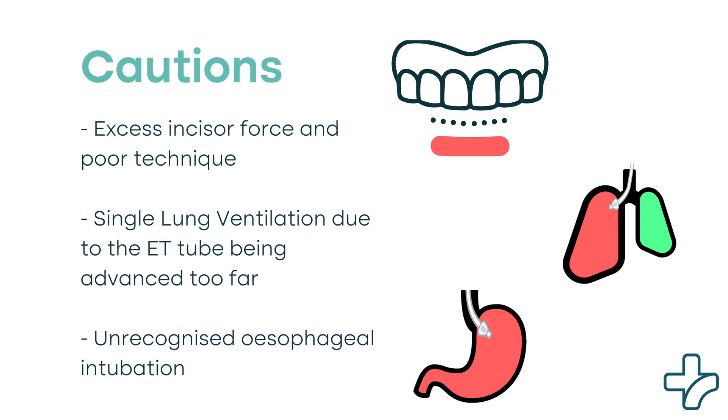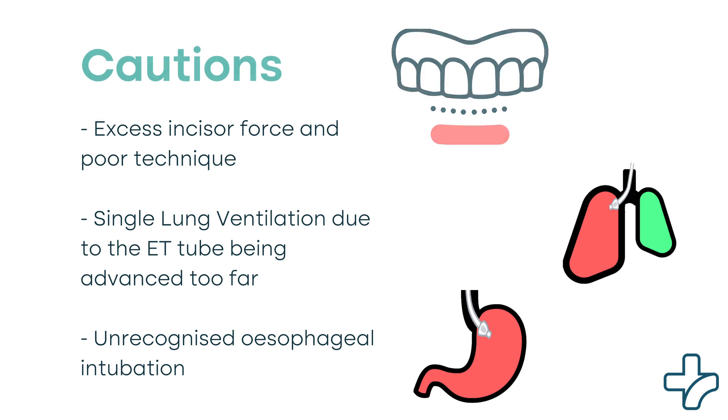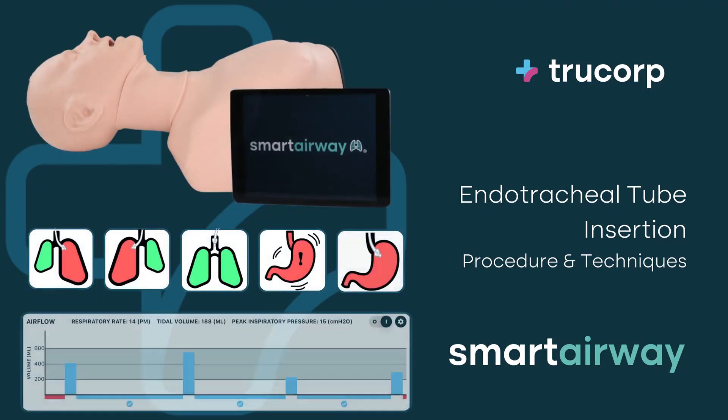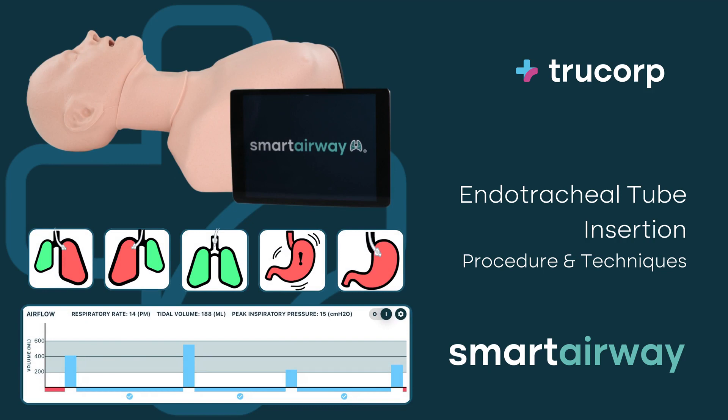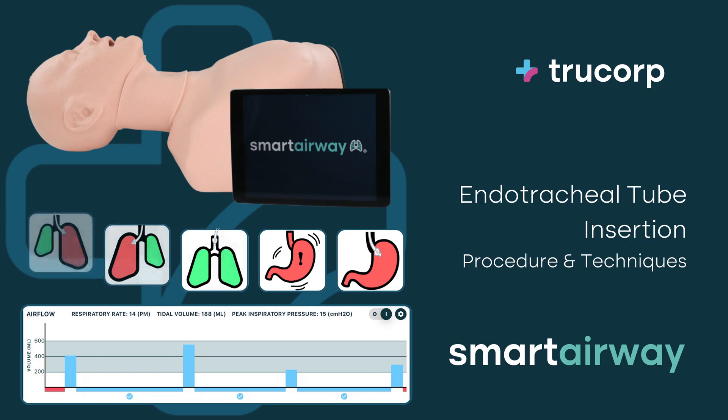Unrecognized esophageal rather than tracheal intubation is a fatal complication. Smart Airway will identify and give feedback on successful placement of the ET tube and initial ventilations, and identify complications such as unilateral main bronchus intubation and esophageal intubation.